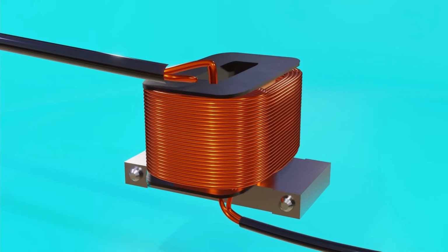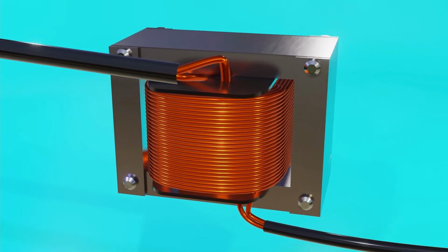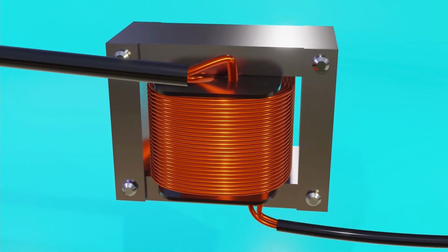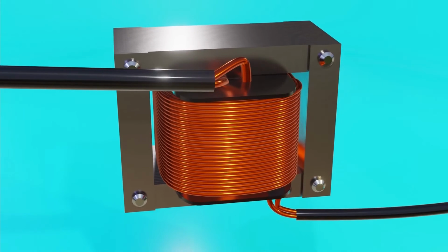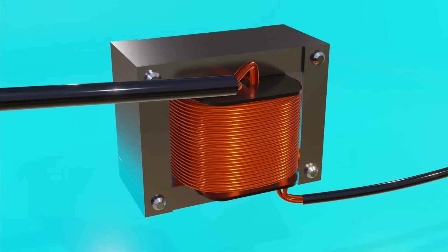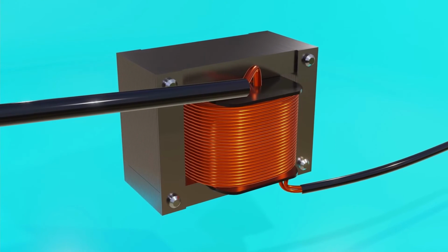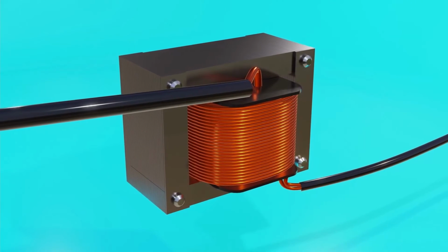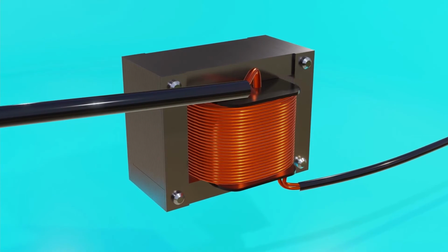One of the most commonly used solutions are the steel sheets with small silicon percentages, around 4%, which are also electrically isolated from each other. That is, not only does the material have a higher coefficient of resistivity, but also its design of sheets decreases cross-section, which is another variable that increases the resistance of a component. In brief, we reduced the eddy currents as much as we could.